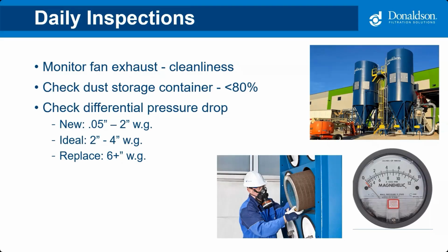It's also good to check it during a pulse cleaning cycle, because that's sometimes where you can catch a plume of dust during a pulse that might be indicative of the fact you've got a leak or damage somewhere in the system. The dust storage container, that dust bin that's either beneath the collector or elsewhere using some sort of conveyance system, you want to check to make sure it's not overfilling.